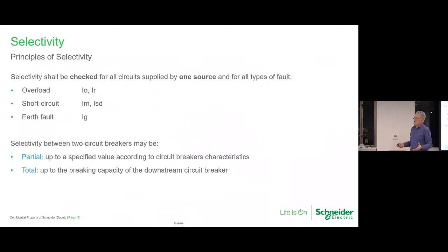But who knows what your fault's going to be? Who knows where that breaker is in the network in relation to what the prospective fault level that you've actually analysed is. So it might be fine. So, or it's very highly unlikely that you're ever going to get a short circuit in this particular circuit for one reason or another. And one of them I can give you is power factor.